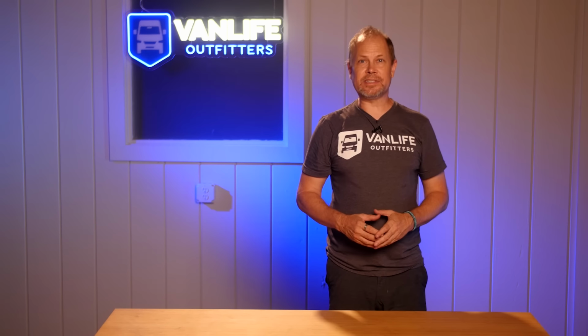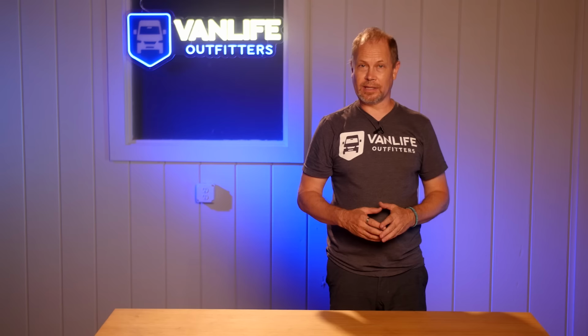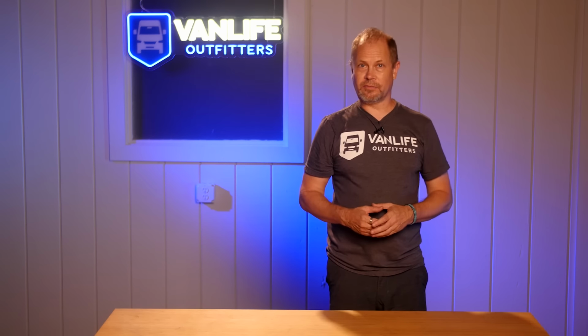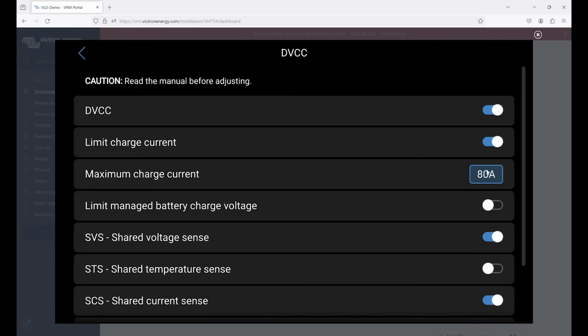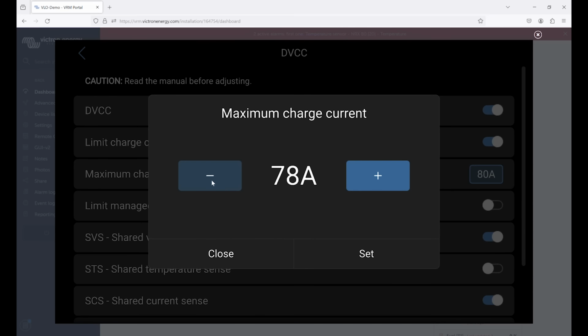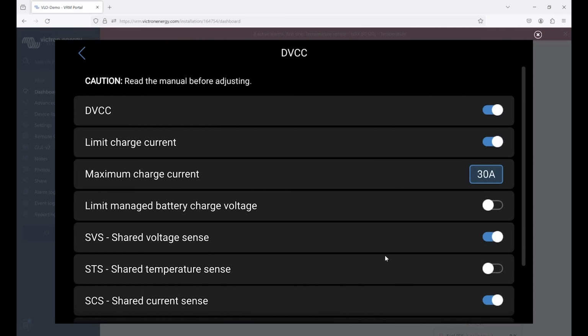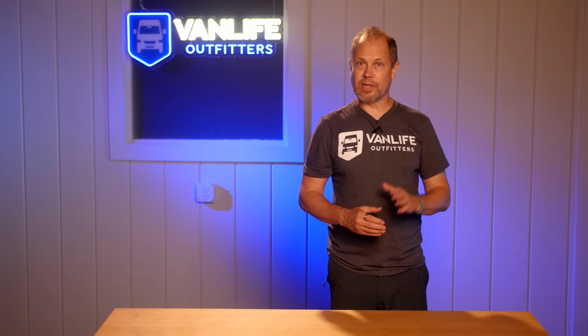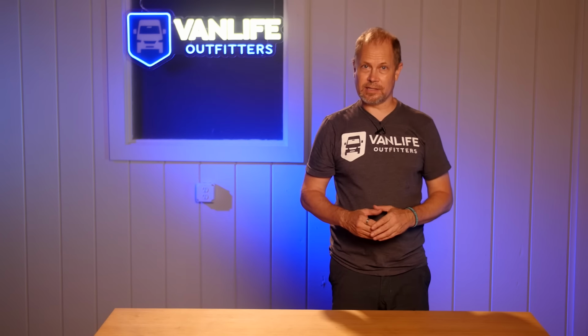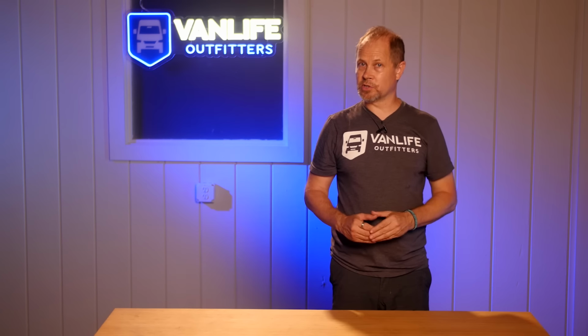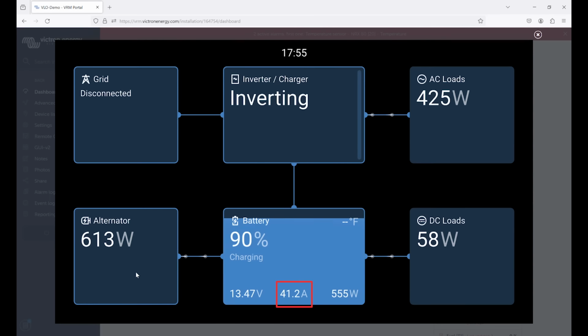Now let's demonstrate how DVCC can account for loads that are monitored by something like a Multi-Plus or a smart shunt that was configured as a DC meter. First, I'll go back into the DVCC settings on the Cerbo and limit it to a max system-wide of 30 amps of charging. Then we'll disconnect the multi-plus from shore power, so the only charger in the system is the Orion XS, which is still configured for a maximum charge of 45 amps. First, we should notice that the charge to the battery is reduced to 30 amps. That's cool. The DVCC settings are overriding the internal Orion maximum charge.